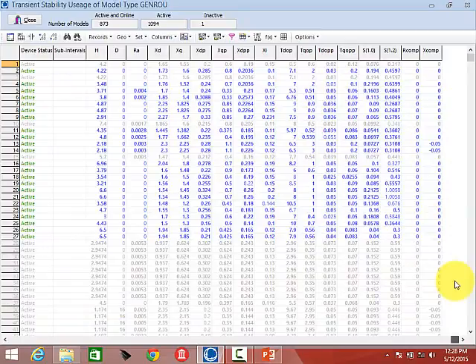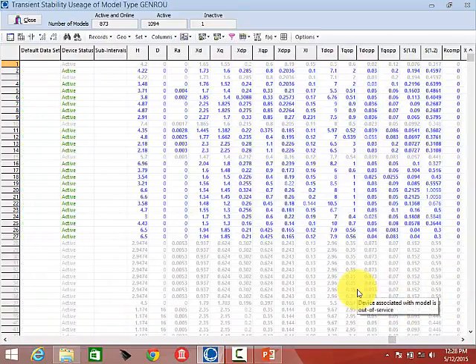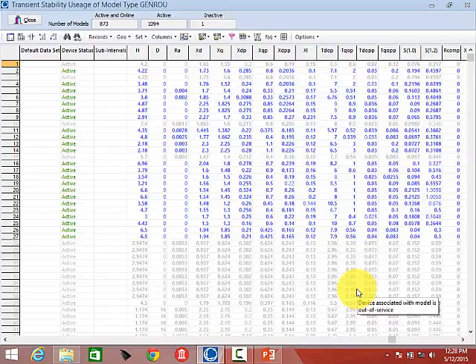The GenROU dialog shows every parameter for every GenROU in the case in a case info display. If you're not familiar with PowerWorld case information displays, the gist is you can get access to a lot of this data — you can send it out to Excel, save it, save it in AUX files, quick plot it, and all sorts of different things. All this data is enterable as well. I use this display a lot when running a model to check whether a parameter is an outlier or not.